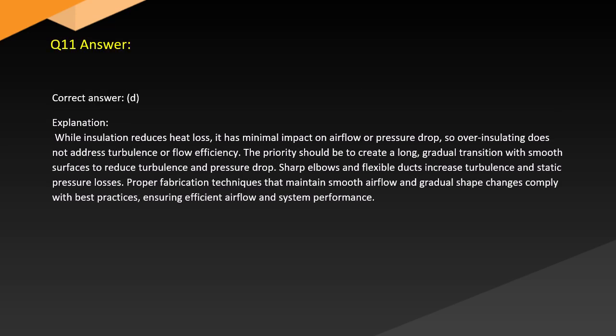Answer. Correct answer: D. Explanation. While insulation reduces heat loss, it has minimal impact on airflow or pressure drop, so over-insulating does not address turbulence or flow efficiency. The priority should be to create a long, gradual transition with smooth surfaces to reduce turbulence and pressure drop. Sharp elbows and flexible ducts increase turbulence and static pressure losses. Proper fabrication techniques that maintain smooth airflow and gradual changes comply with best practices, ensuring efficient airflow and system performance.